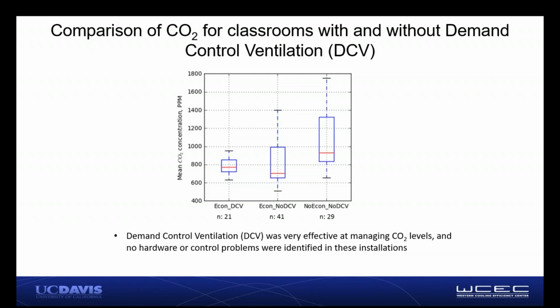On the right-hand side are the rest of the classrooms that did not have demand control ventilation. We also separated them by classrooms with economizers and without. You can see here's where the CO2 range was really significant, and here's where we saw really high CO2 levels, because you don't know. Whereas with the demand control ventilation systems, all those classrooms had CO2 sensing, and we generally found it was very effective at managing CO2 levels, with no hardware or control problems identified in those installations.